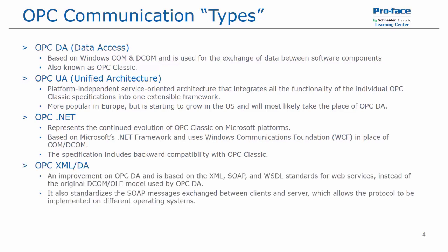And then there's OPC XML DA. It's an improvement on the OPC DA standard and is based on the XML SOAP and Web Services Description Language, or WSDL, standards for web services, instead of the original DCOM or OLE model used by OPC Classic. It also standardizes the SOAP messages exchanged between clients and servers, which allows the protocol to be implemented on different operating systems. And don't worry about all the acronyms that are listed here.